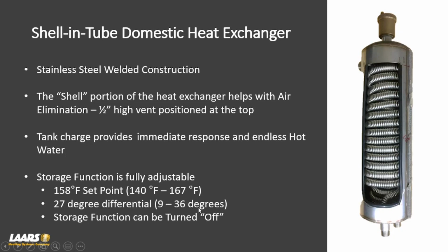We have a differential range that they could get in and adjust. Example of that is from 9 to 36 degrees. And again, that is on the hydronic side. And this storage function can be turned off. So example, you have a customer that's going away for a long vacation. Maybe it's summer months and that boiler is going to keep firing, 3, 4, 5 times a day just to be in tank charge mode. You can get into the programming and very simply turn that feature off.